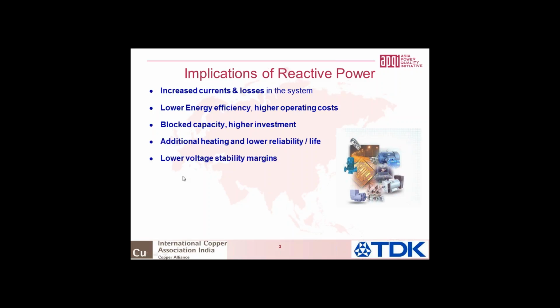And of course, you have lower voltage stability margins, because whenever the current from the generating station flows through a series impedance comprising resistance and reactance, there will be a voltage drop. So the receiving end voltages will be much lower than the sending end voltages. Even if the alternators are generating 11 kV, at the receiving end it could be much lower, which means I have a lower voltage stability margin, which has its own secondary and tertiary effects. Like if you have a lower voltage, then the motors tend to draw a higher current. So these are the 5 major implications of reactive power in the system, which are very well known.